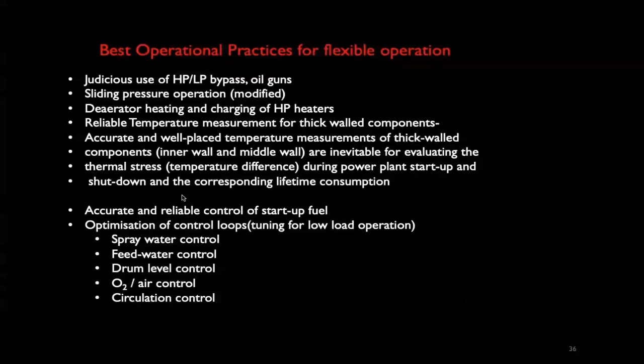Some best operational practices, what we had seen about the opening of HP bypass. See, this is a thing which we have been doing 20 years back, 25 years back, when I used to be in the plant. I used to operate it many times, and this is very safe. But today, if you talk to people with less experience, they are always fearful. Like if you open the HP bypass, drum unit will trip on drum level. I don't know what kind of fear they have.